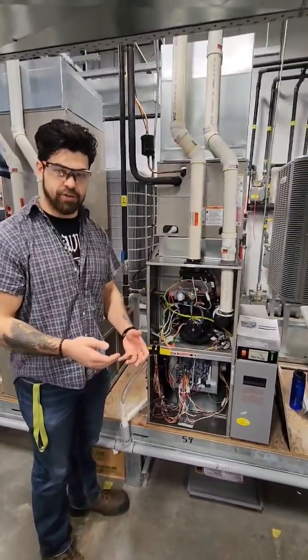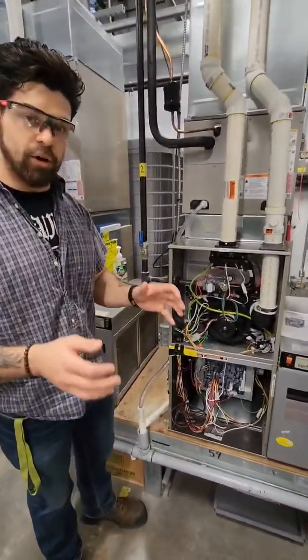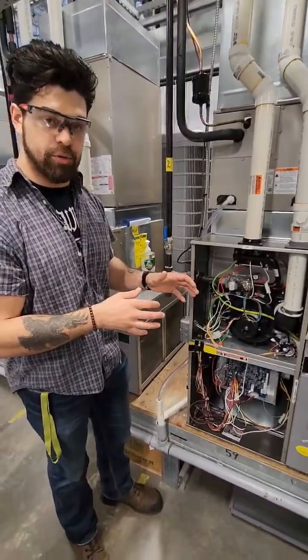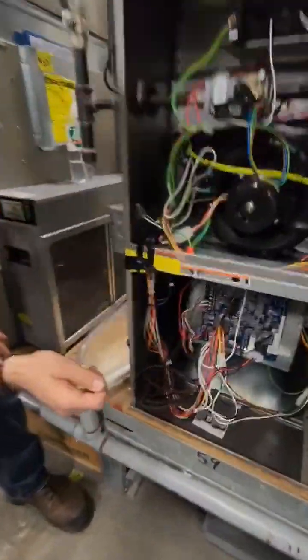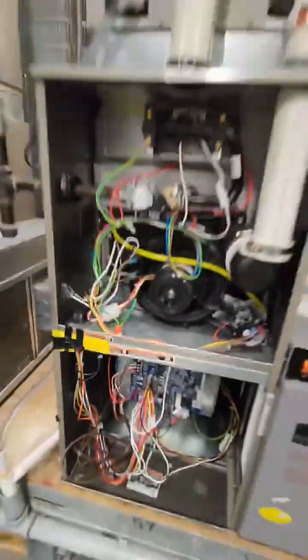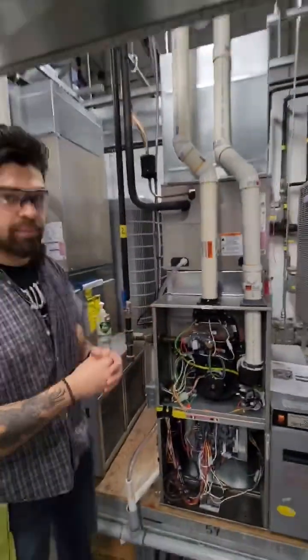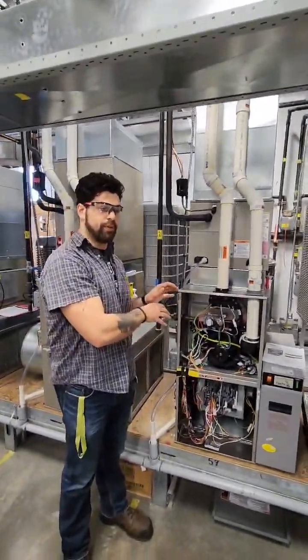For other technicians watching this, a useful tip involving any furnace to begin your troubleshooting would be to simply take a jumper cable and jump terminals R and W. Disconnecting one and jumping the terminals with any wire you may have available in your kit or van can immediately eliminate the thermostat from the equation and bring your troubleshooting back to all the other components of the furnace, eliminating issues with the thermostat.